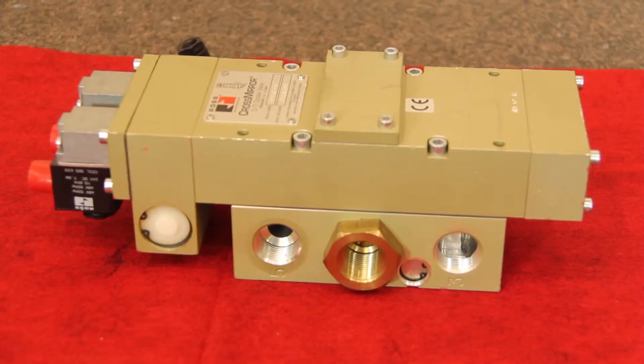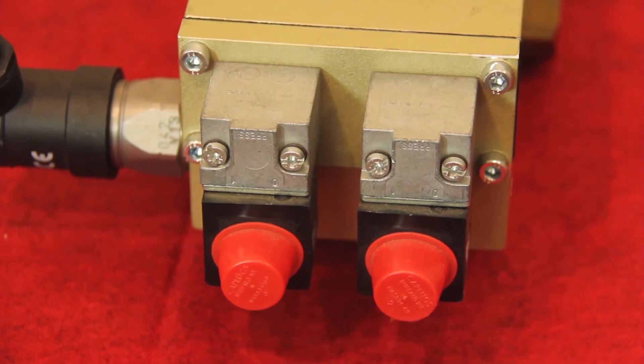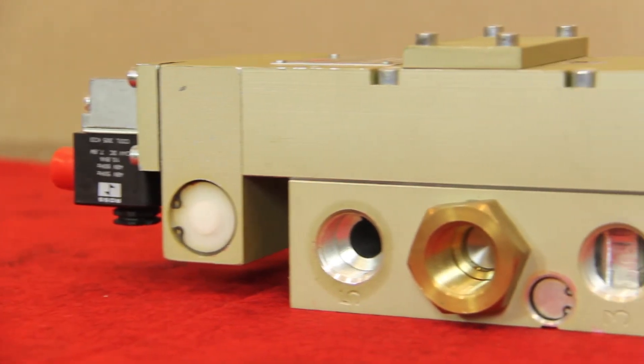The valves are third-party certified to Category 4 Performance Level E for ISO 13849 and meet the safety-related parts of the control system required under that standard, as well as the ANSI and CSA standards, the new robotics standard from ISO, and the Brazilian NR-12.